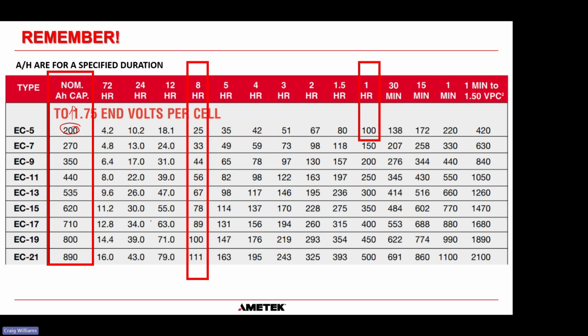But that's not the end of the conversation. They say, okay, 200 ampere hours at what duration? And I know that ENESYS always usually quote at the 8-hour rate. So if you look at this table here, this column here, at the 8-hour rate, it's saying you will get 25 amps. And if you multiply 25 times 8, this value here, that equals 200 amps.